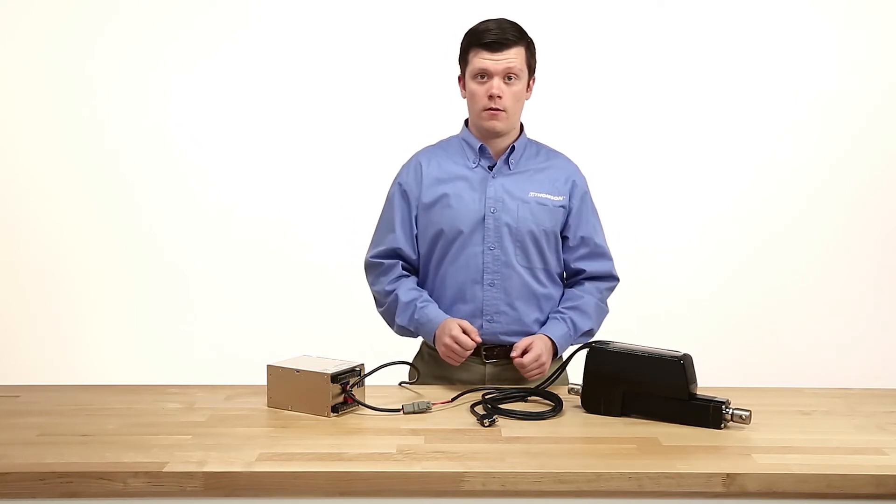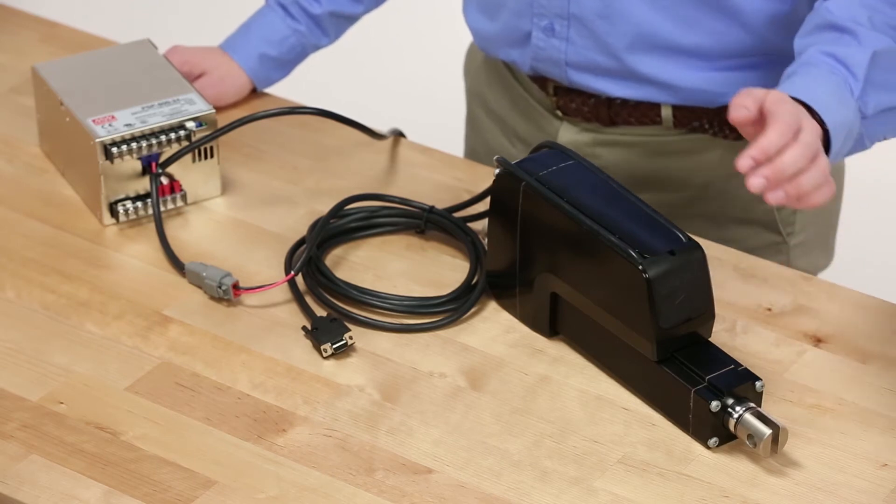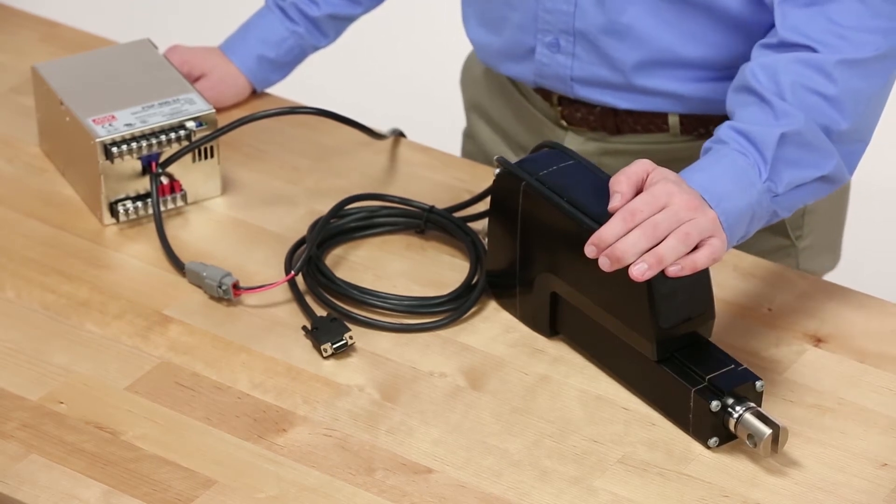Inrush current should also be considered. Most of our actuators will draw three times the rated current to start the motor.